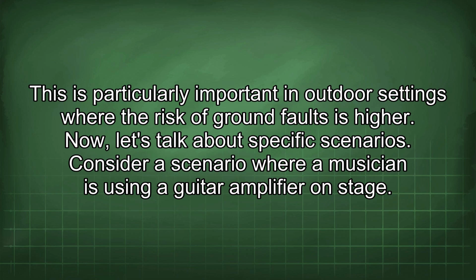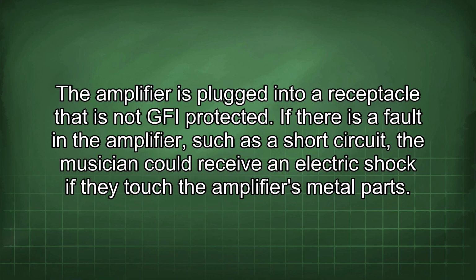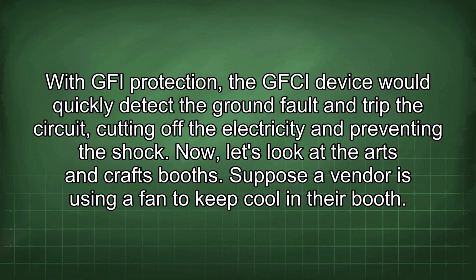Now let's talk about specific scenarios. Consider a scenario where a musician is using a guitar amplifier on stage. The amplifier is plugged into a receptacle that is not GFI protected. If there is a fault in the amplifier, such as a short circuit, the musician could receive an electric shock if they touch the amplifier's metal parts. With GFI protection, the GFCI device would quickly detect the ground fault and trip the circuit, cutting off the electricity and preventing the shock.